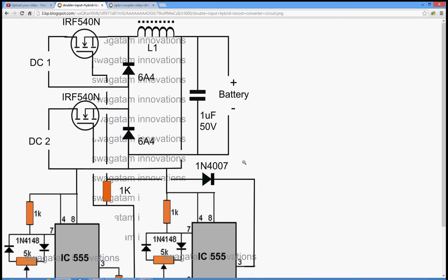So for example, when they go into float, it says, okay, well, the battery voltage is sitting right like this. I'm only going to pass this amount of current right now. Meanwhile, the other charge controller is saying the same thing. So ultimately, you're passing more current than float wants to see. That's what I'm talking about.